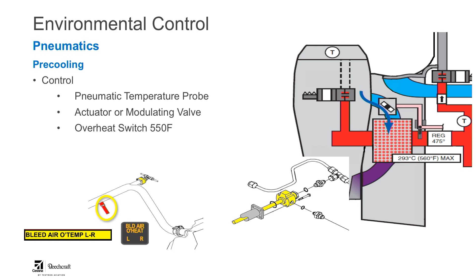Now there's another system that's tied in here on models 525 and 525B, as well as 525A serial 462 and on. We call it the Max Cool feature or Max Cool operation. And going back to that little T I mentioned just a minute ago, it goes to a solenoid valve, which is normally closed and is powered open when certain conditions exist.